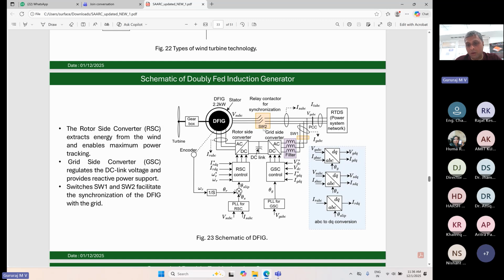And from the grid perspective, it looks as if 50 Hertz power is injected from the machine. In the case of super synchronous mode of operation, the wind speed increases, so there is excess power beyond 50 Hertz. That is drawn out from the rotor side, and the 50 Hertz component directly flows through the grid, and through the rotor side converter and grid side converter, this additional component of power is fed to the point of common coupling, making it more steady throughout the operation at various wind speeds.